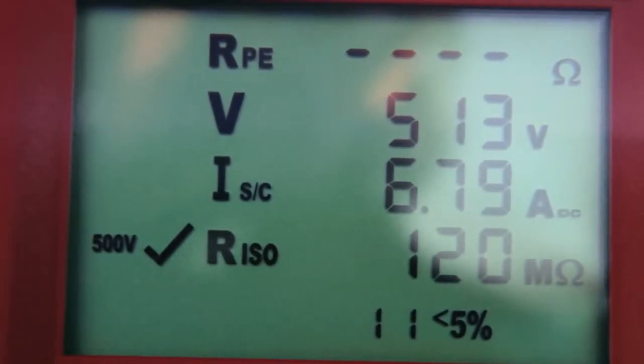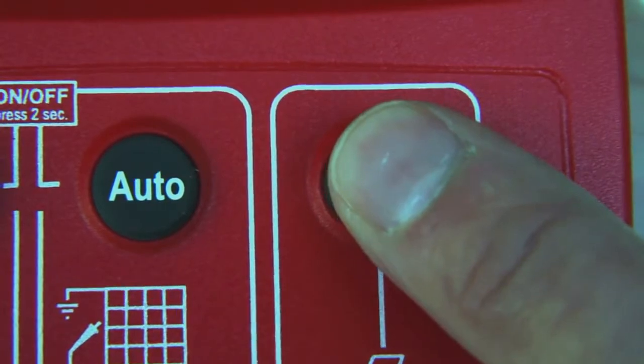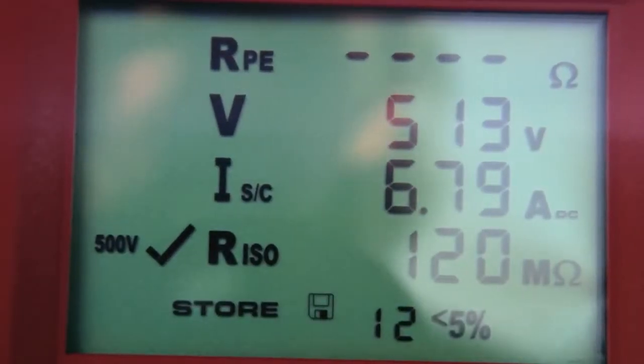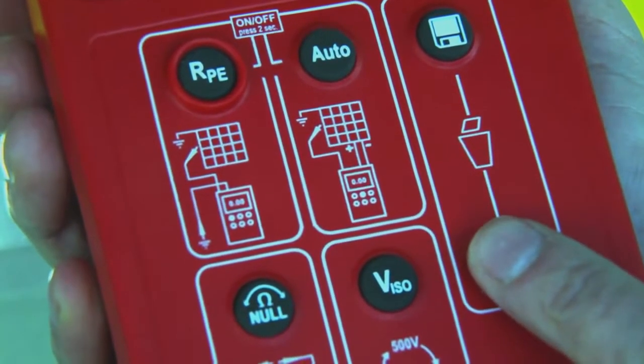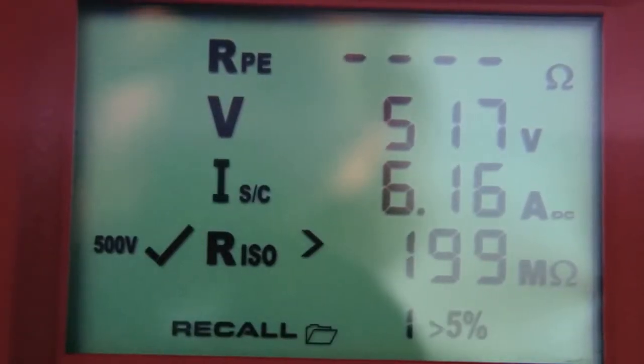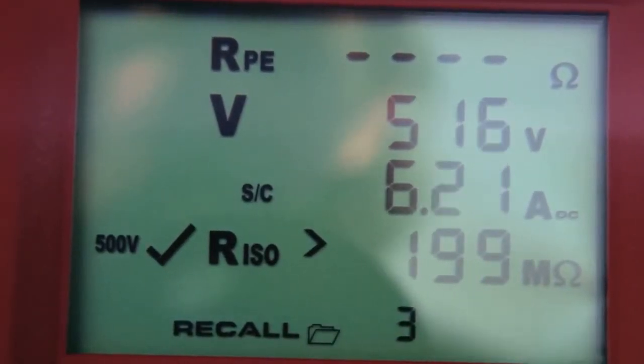The measured values for voltage, short circuit current and insulating resistance can be stored by means of the Store key and can be recalled for control at any time by means of the Recall function.